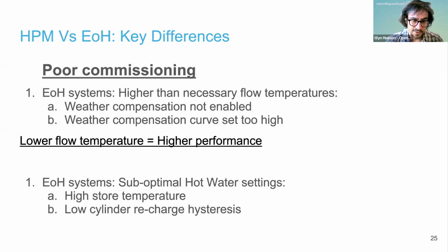We also saw that there was suboptimal hot water storage commissioning. The hot water was often stored at a very high store temperature with a very low hysteresis. So as soon as a small amount of hot water was drawn off, the heat pump would almost immediately kick in to try and reheat the tank, even though it's still piping hot. And that results in poor hot water performance.